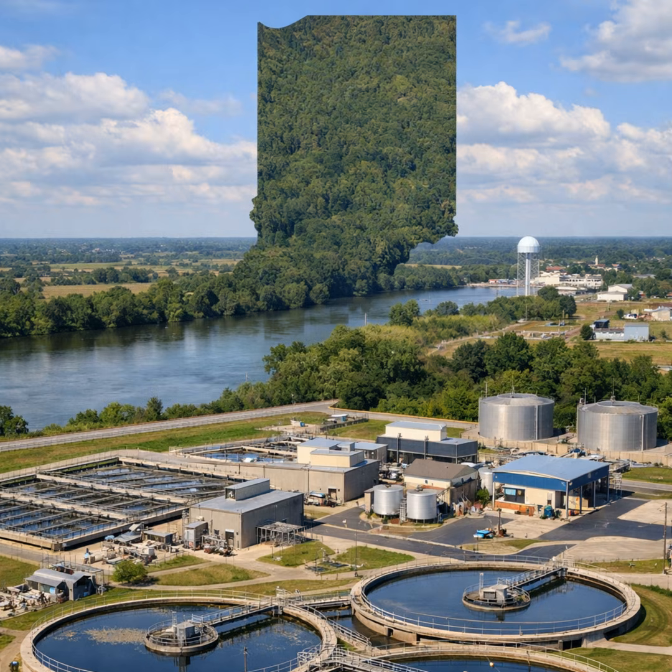Also, your return activated sludge rate must be gradually increased so the aeration tank and the secondary clarifier are not hydraulically overloaded and the solids loading rates are not exceeded.